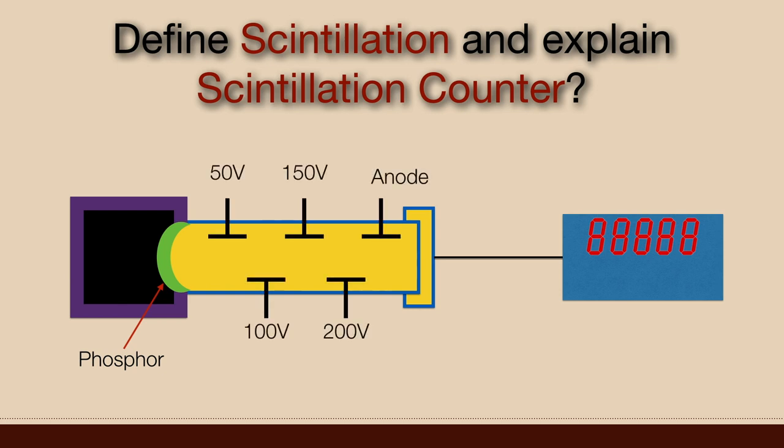PMT is photomultiplier tube. It works on the phenomena of secondary emission. It is long metallic tube. A sensitive photocathode is placed at one end of the tube and series of electrodes called dynodes are arranged in the tube.